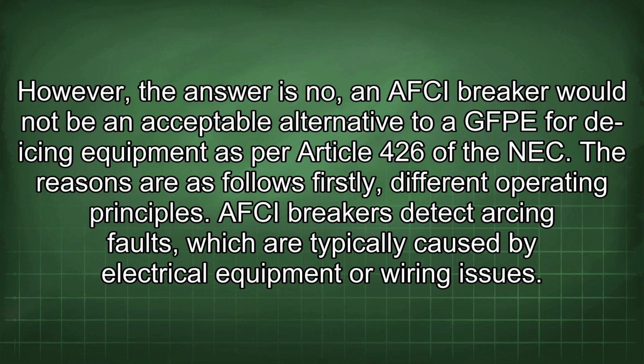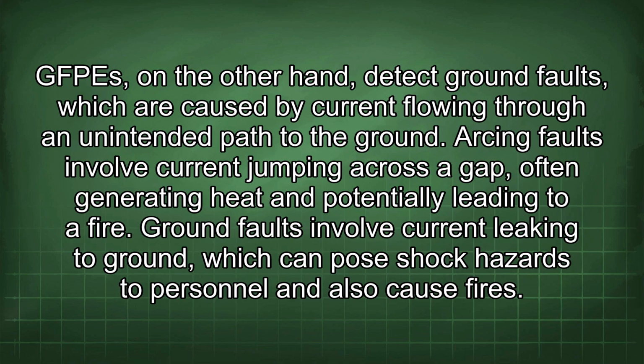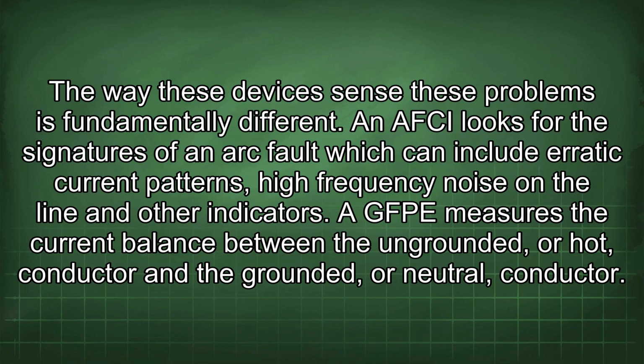Firstly, different operating principles. AFCI breakers detect arcing faults, which are typically caused by electrical equipment or wiring issues. GFPEs, on the other hand, detect ground faults, which are caused by current flowing through an unintended path to the ground. Arcing faults involve current jumping across a gap, often generating heat and potentially leading to a fire. Ground faults involve current leaking to ground, which can pose shock hazards to personnel and also cause fires. The way these devices sense these problems is fundamentally different.